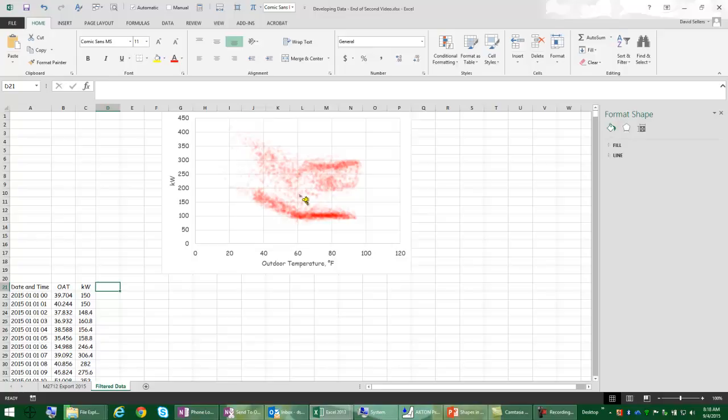For instance, if we filtered out all the hours between, just to take a stab at, I guess, 7 in the morning and 5 in the evening, we may see this cloud get very light or disappear, which would basically say, oh, that's the energy associated with things that are going on in the building, and this happens to be a hotel, so like meeting rooms being used and stuff like that, and this is the base load.